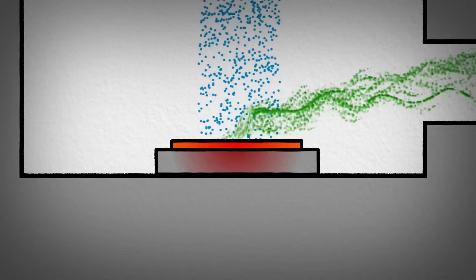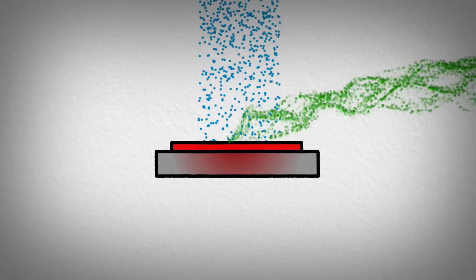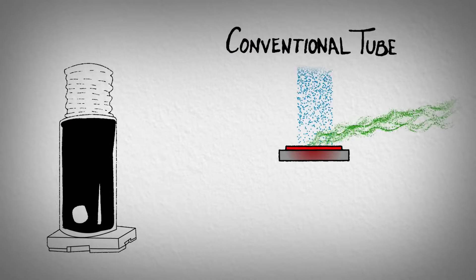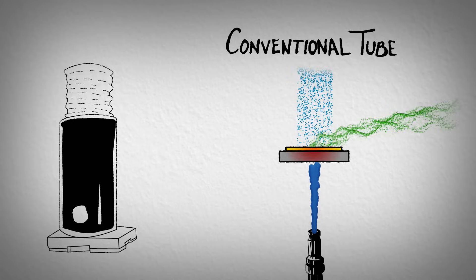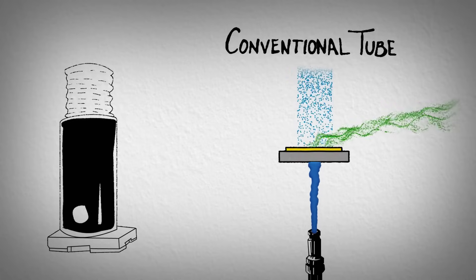In addition to creating X-rays, a large amount of the energy is converted into heat, requiring the anode to be cooled. In the traditional tube, the large footprint of the wide electron beam limits heat dissipation, requiring the anode to be water-cooled.